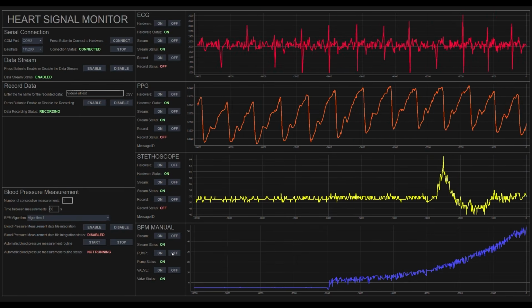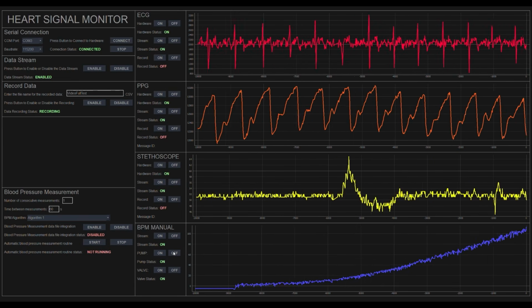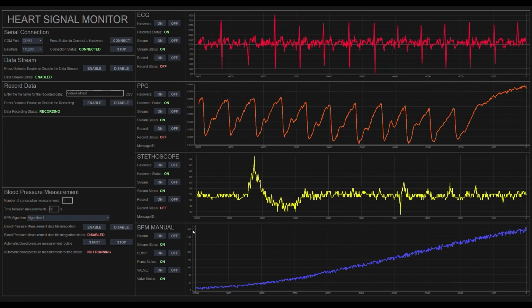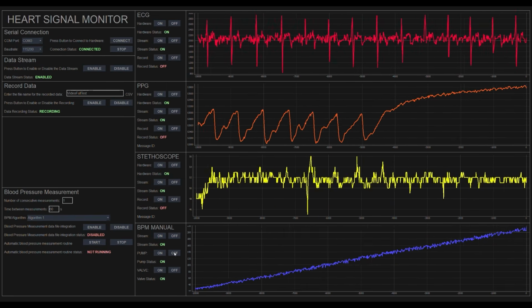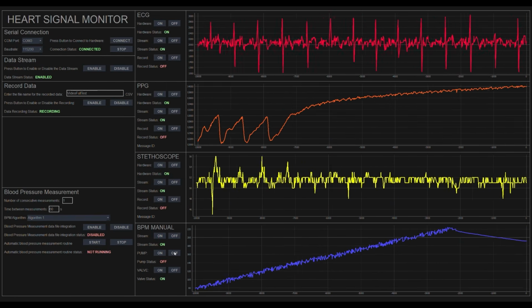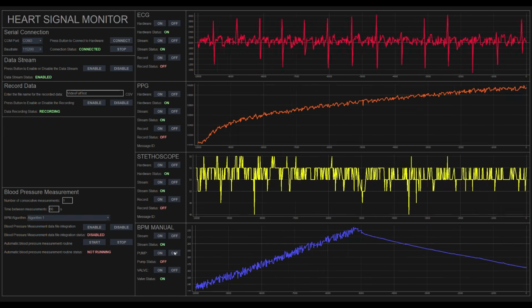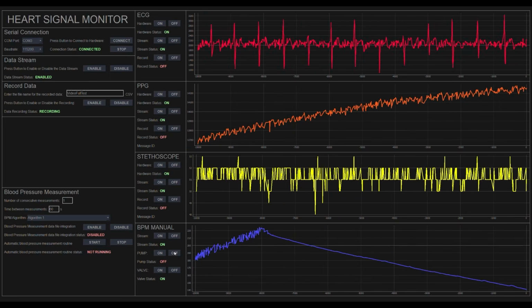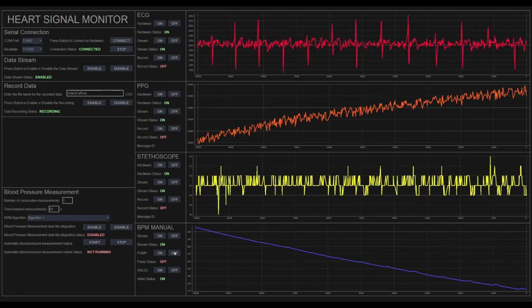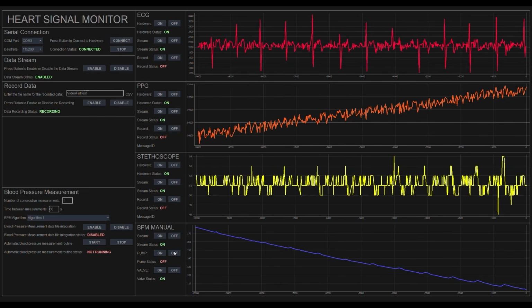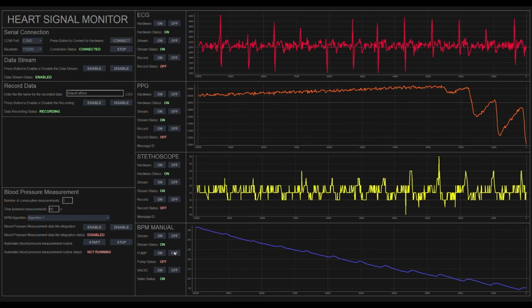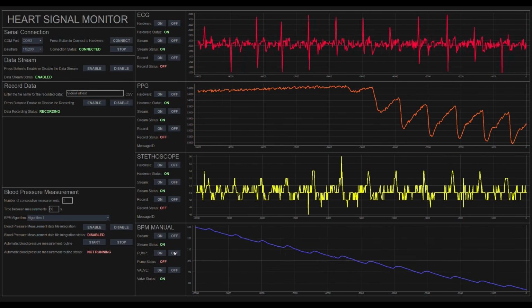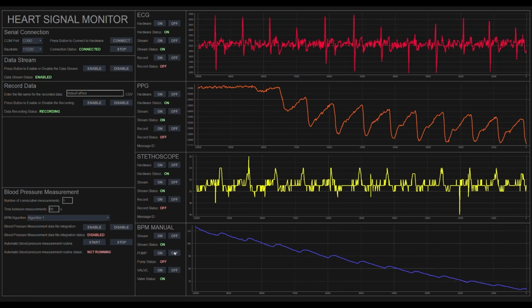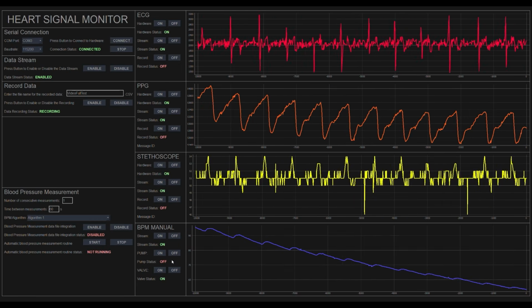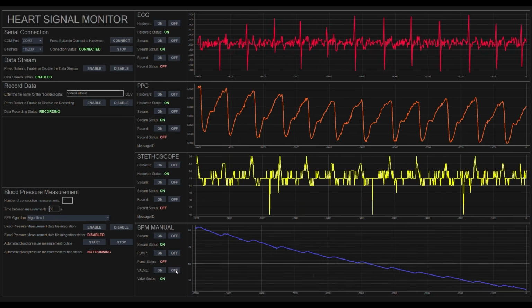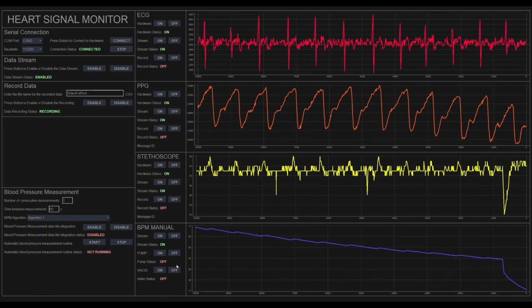We want to inflate to around 200 just to make sure, and slowly deflate it. Here we can take a look at the value. You can see the cuff slowly starting to deflate here, and make sure to keep the orange signal in mind, so there are no oscillations on it now. But as the pressure in the arm cuff is slowly decreasing, you'll start to see right now the small pulsation starting. That's the blood flow being re-established in the finger. And you can also see a similar thing in the stethoscope signal, but that's something we'll analyze in the data section of this video. And now we can completely deflate.